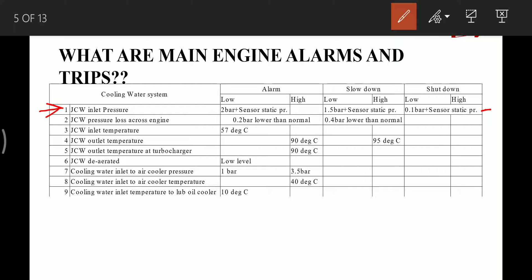Jacket cooling water pressure loss across the engine: at 0.2 bar below normal it gives alarm and at 0.4 bar below normal it gives slowdown — to ensure no obstruction in water flow. Jacket cooling water inlet temperature: low alarm at 57°C. Jacket cooling water outlet temperature: high alarm at 90°C and slowdown at 95°C. Jacket cooling water outlet temperature at turbocharger: high alarm at 90°C.